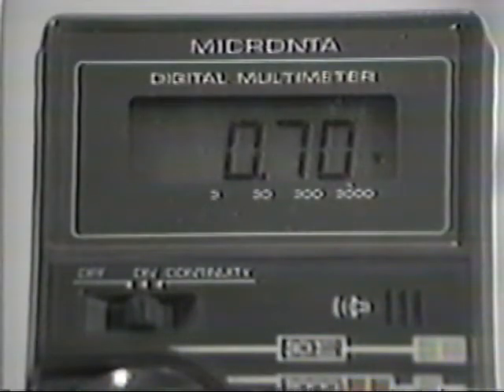The ground sides of the bell and light come together here and are connected to CLA module number 3 terminal here. In order to give a low water alarm then, the light and bell must find ground through the module. Whether or not the module gives a ground to the light and bell depends on the voltage at terminal number 2. This is a very low voltage, but it can be measured with a digital voltmeter.